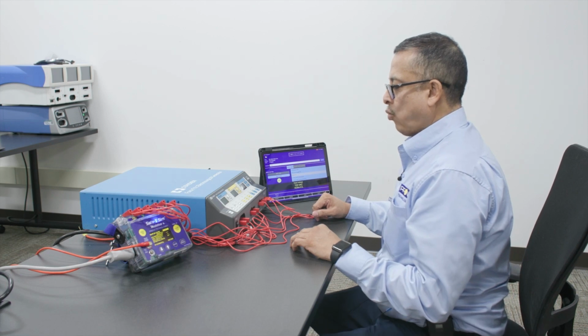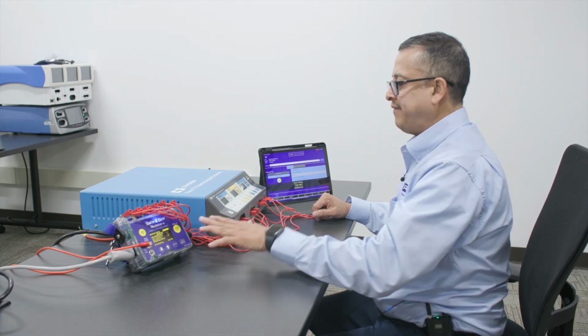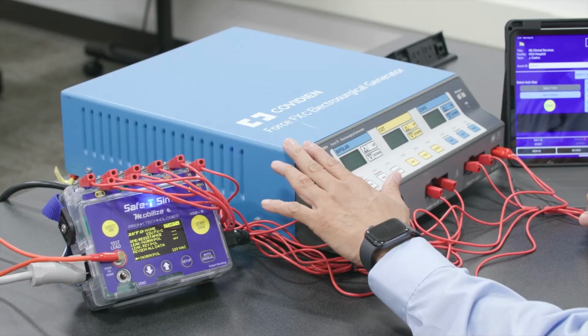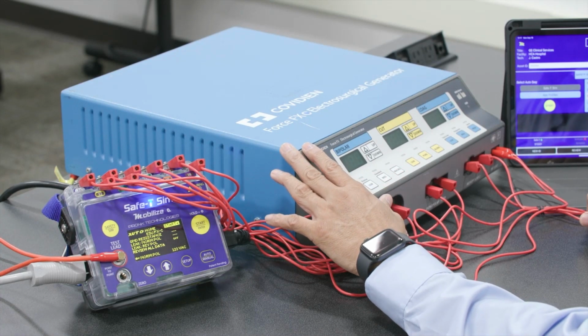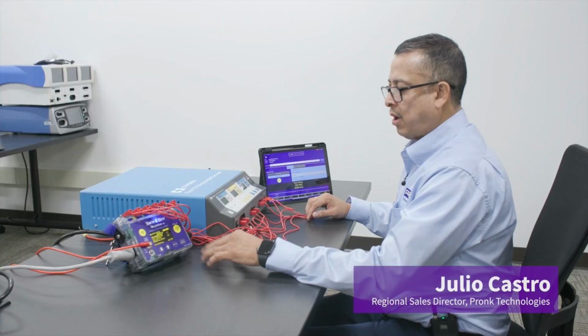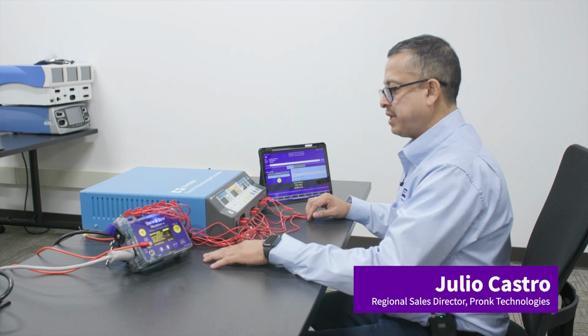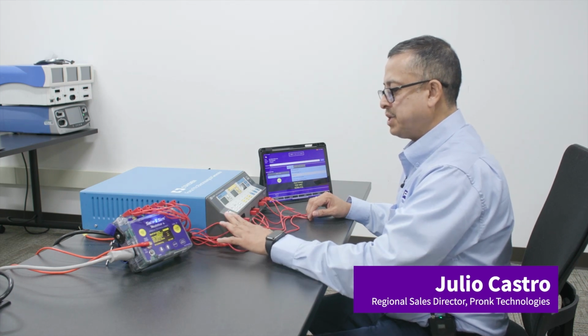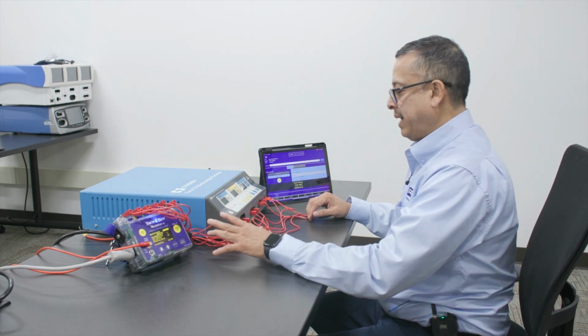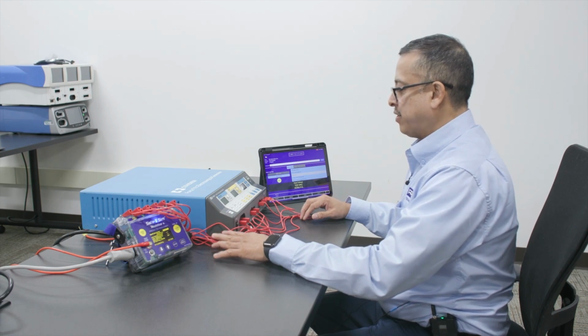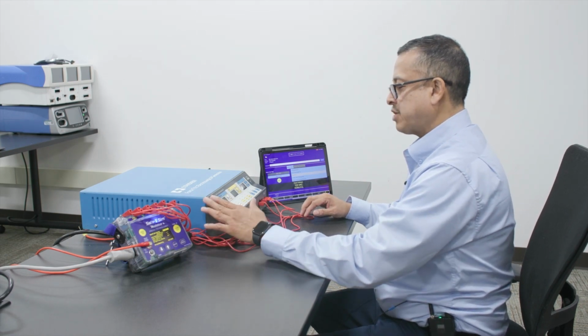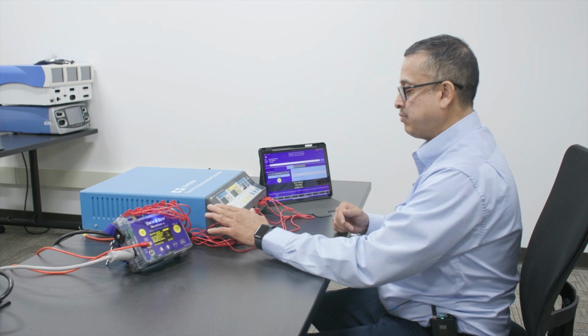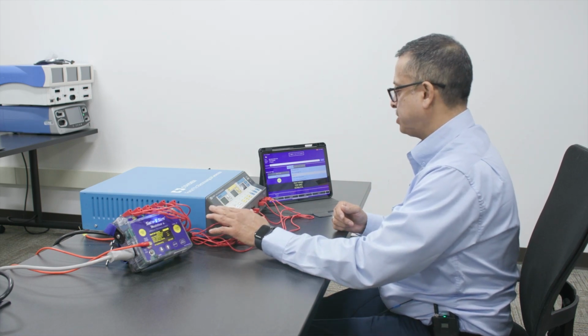We're going to go ahead and walk through how to perform electrical safety tests on this ESU Force FXC. It's important that we make sure we follow our safety protocols and our proper PPE before doing any service on any medical device, particularly on these ESU devices. Before we begin, we want to make sure we've configured the test properly for what the manufacturer requires in terms of the testing that is necessary and what the pass-fail limits are.